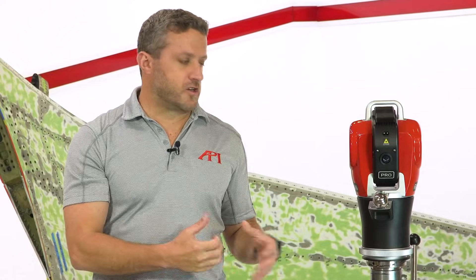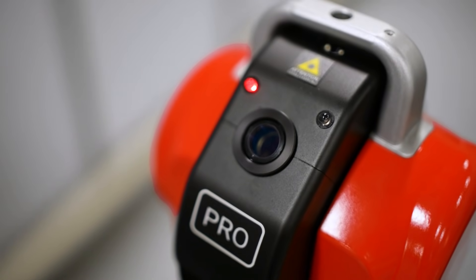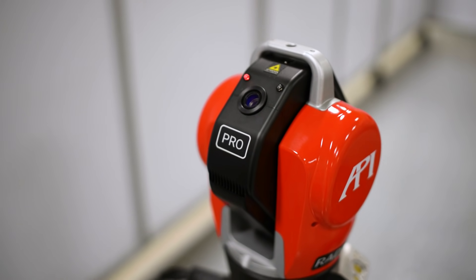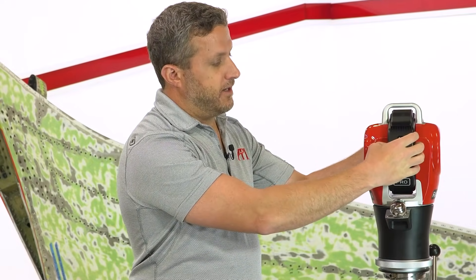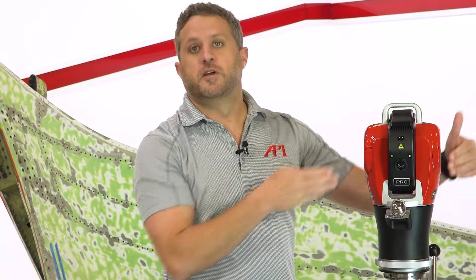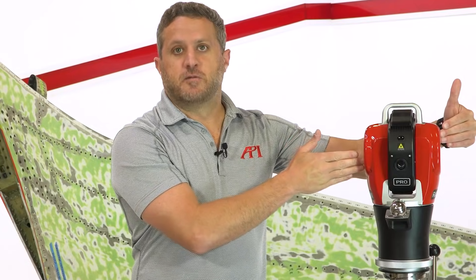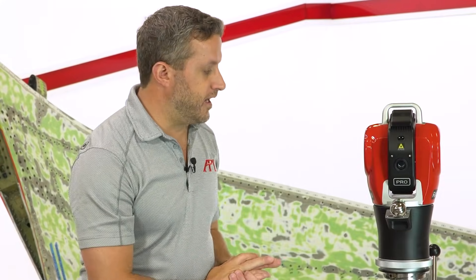To make this tracker as accurate as it is requires that the control box be remote from the tracker head. The design is very simple: you have the gimbal down below, the frame is a unibody design, the laser housing is a unibody design, and it's controlled through a shaft right through the unibody. A lot of competitors use side-mounted motors, not necessarily taking the rigidity right through the unibody head. So again, this is the interferometer laser with ADM support.